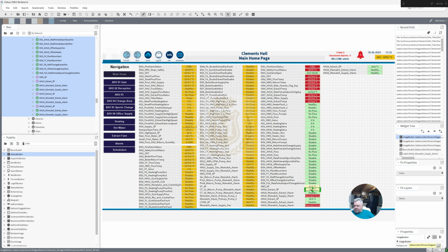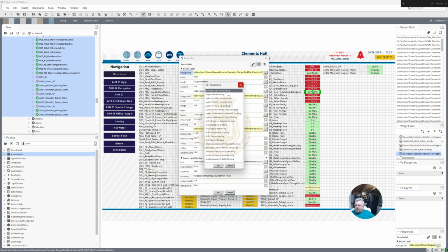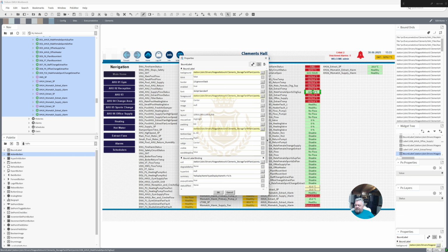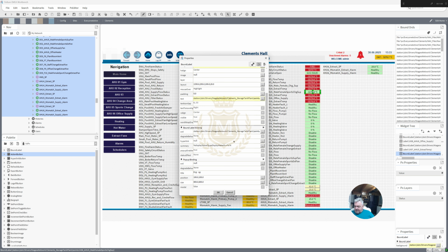But what I'm actually going to do on all these, now I know my mismatches, I don't think I put histories on them. There's alarms on them, but there's no histories. But for example, this temperature here, there's a history on there. So I'll go through every single temperature and I will do this. Kit pop-up binding. Highlight that, Control key C. Put it into the ORD.